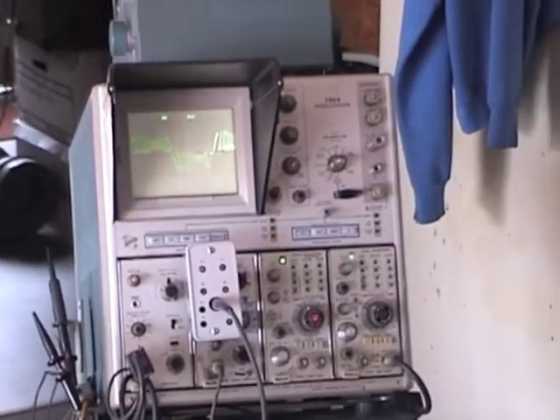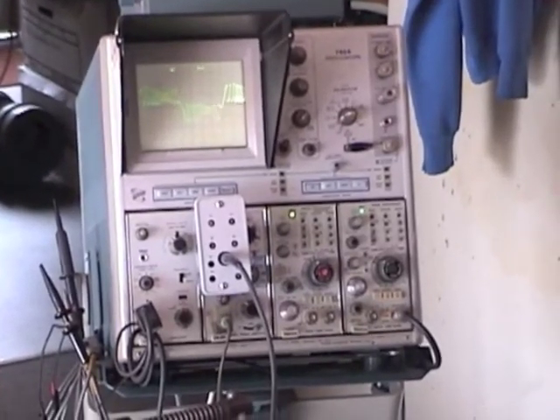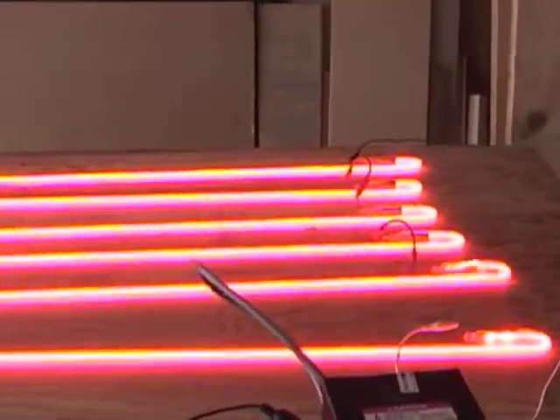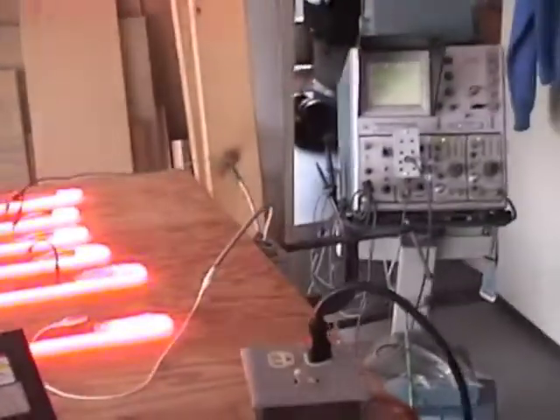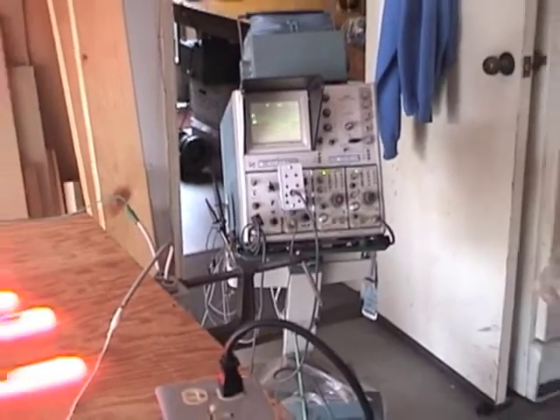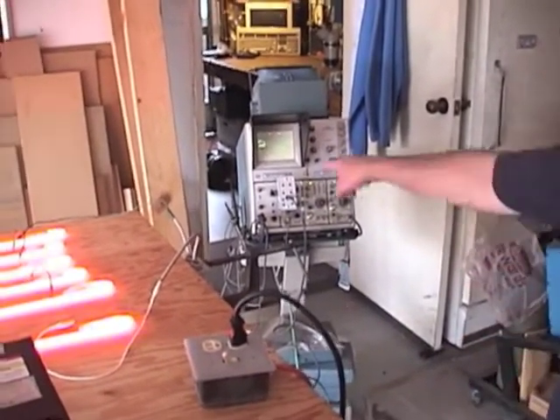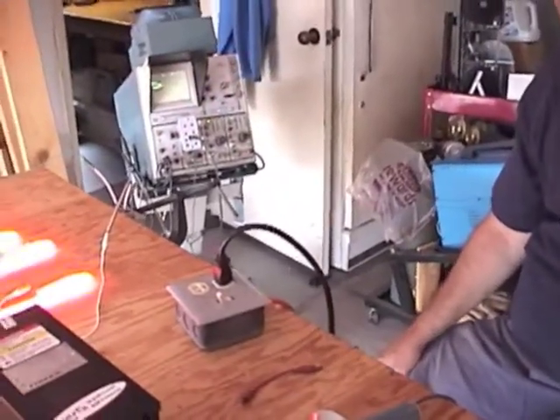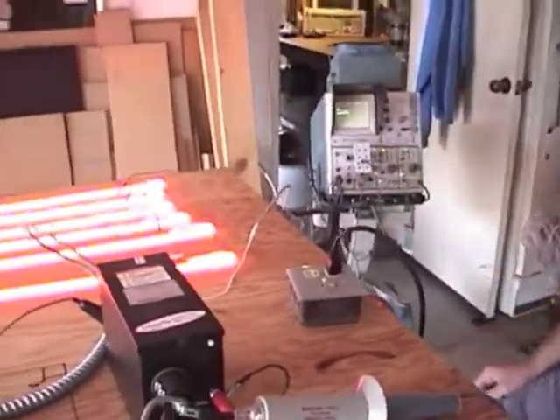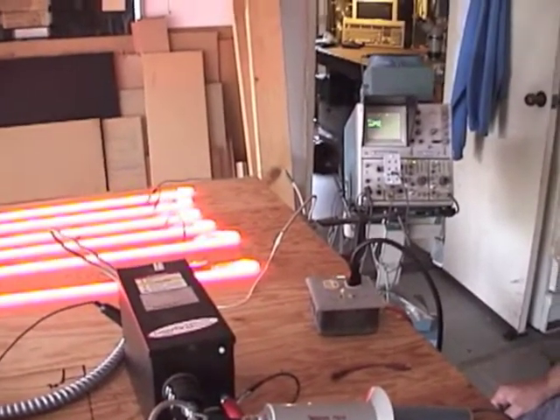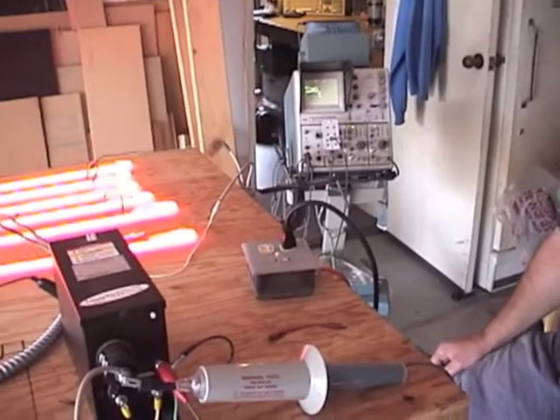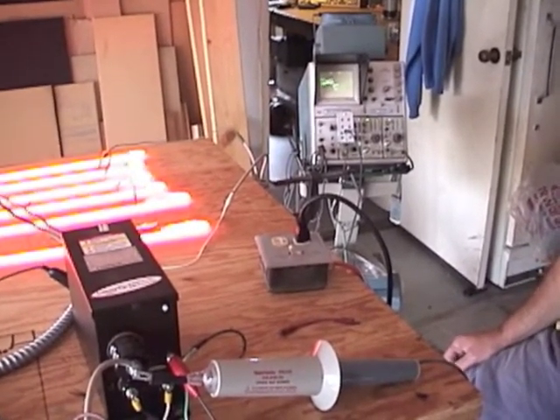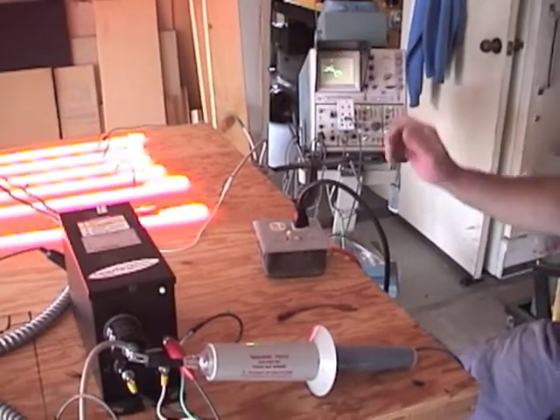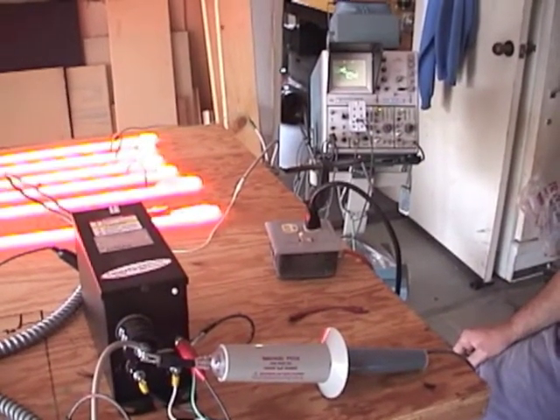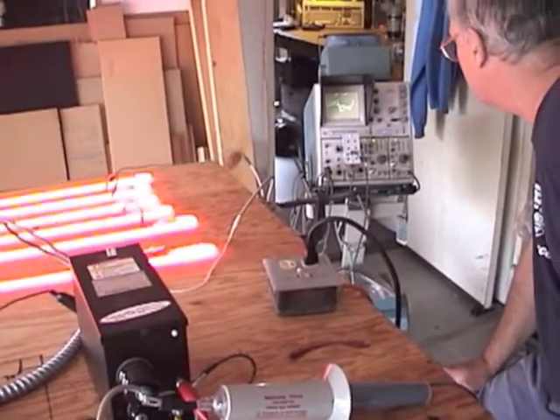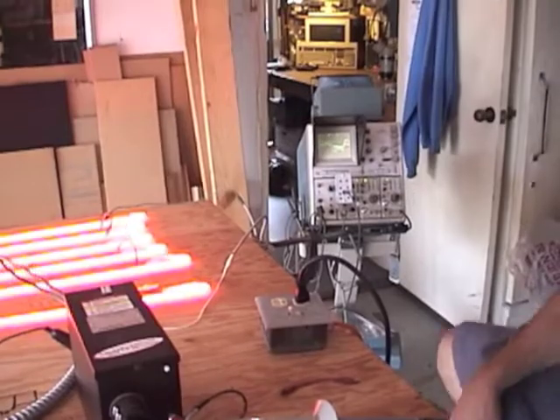Now you've got 10 kV spikes on a secondary that's only supposed to max out at 7.5 unloaded. And it's constantly ringing. In fact, you can see the glass flicker. And that's just by adding two 20-foot runs of GTO and flex. 40 extra feet. You can hear it and you can see it. And if you run this long enough, it'll eventually fail the tranny, because now you're putting 5, 10, 20 kV across a 15 kV tranny.